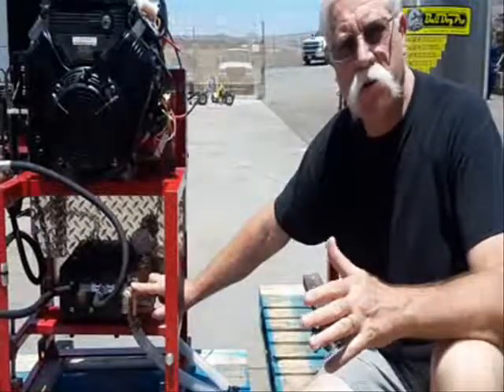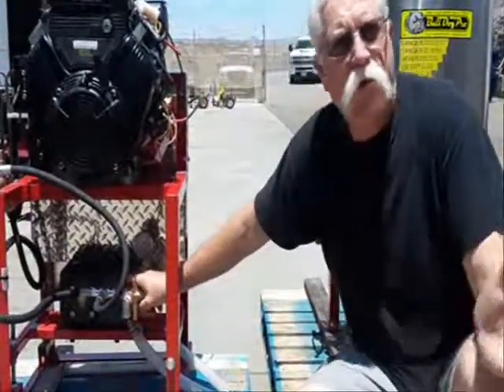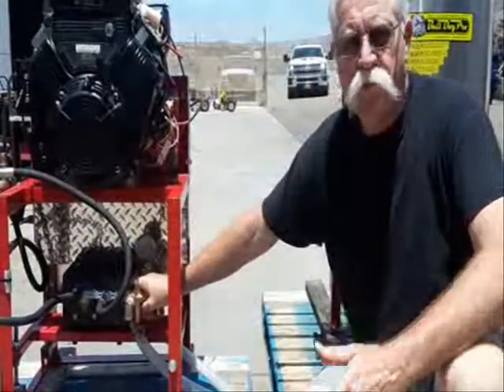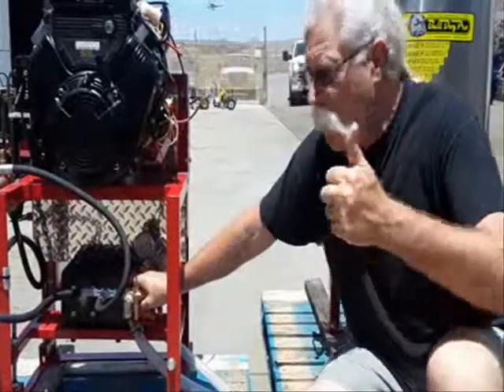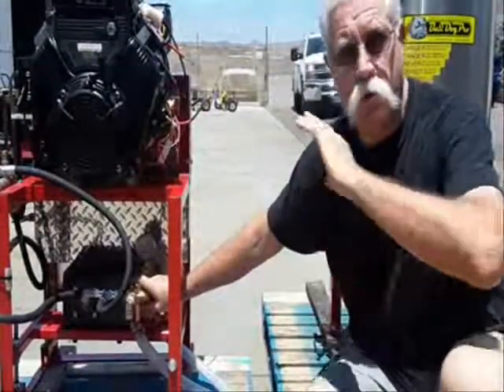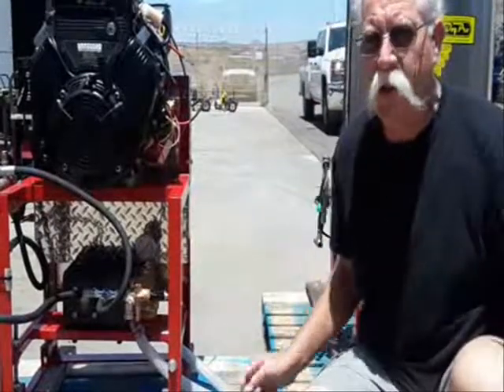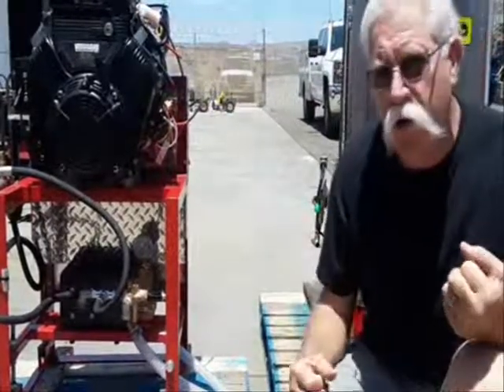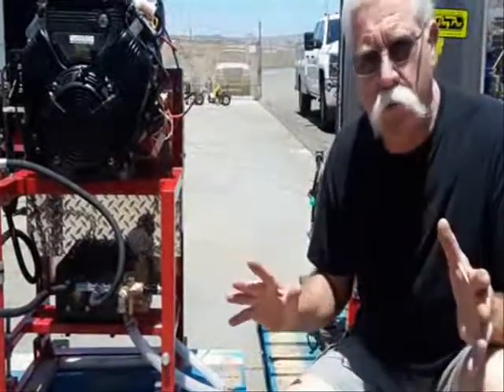You want to make sure that the first thing you do whenever you're testing any pump system is make sure that when you open the gun you get pressure. When you let go of the gun, it goes into a no-load bypass. It doesn't sound like the engine is running hard in horsepower just to keep the thing running in bypass. It should be a no-load bypass.